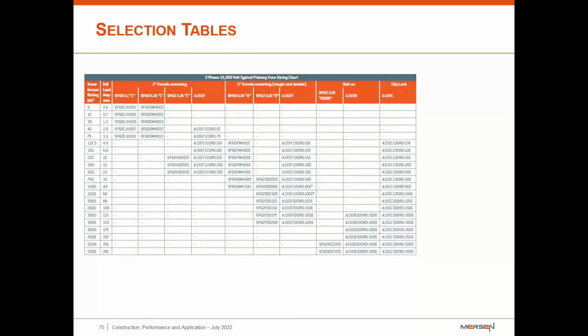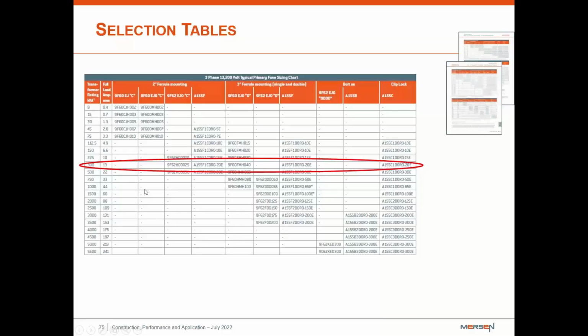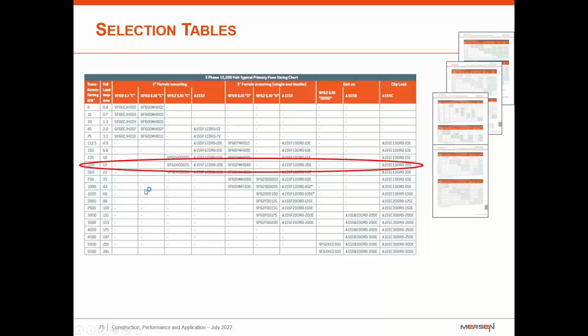So in the actual Advisor, ourselves and online, you're going to see how these are laid out. On the left is going to be the transformer rating in kVA, which this will be your 300, and then our full load amps, and then there'll be the different styles of fuses based on the ferrule types that we're going to have for these. If they're going to be bolt-on or clip-in, and the different applications we have. So it kind of explains itself inside of the tables. There's going to be a wide range of tables available, and if you need these, we can get them to you. They're available online, but upon request, we can get you any information that you need for this.